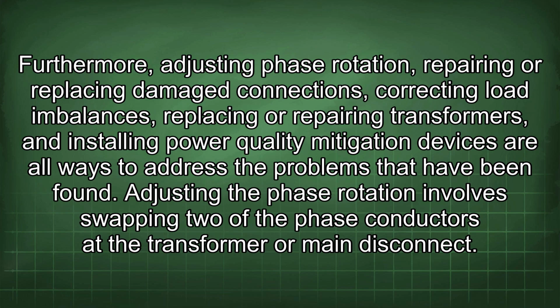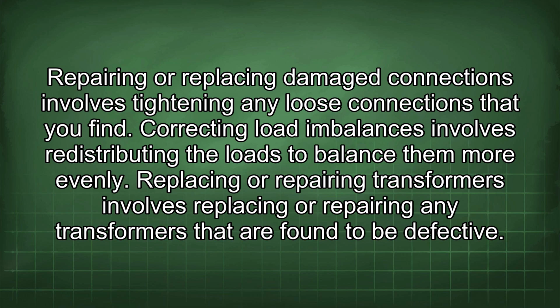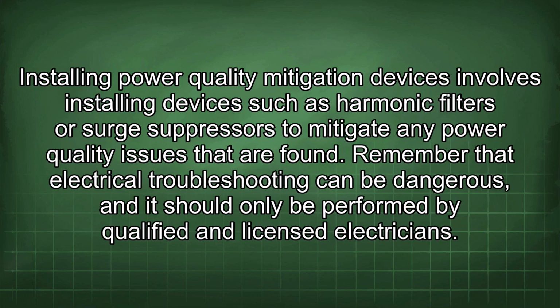Adjusting the phase rotation involves swapping two of the phase conductors at the transformer or main disconnect. Repairing or replacing damaged connections involves tightening any loose connections that you find. Correcting load imbalances involves redistributing the loads to balance them more evenly. Replacing or repairing transformers involves replacing or repairing any transformers that are found to be defective. Installing power quality mitigation devices involves installing devices such as harmonic filters or surge suppressors to mitigate any power quality issues that are found.